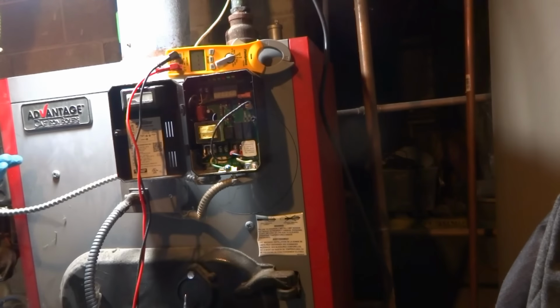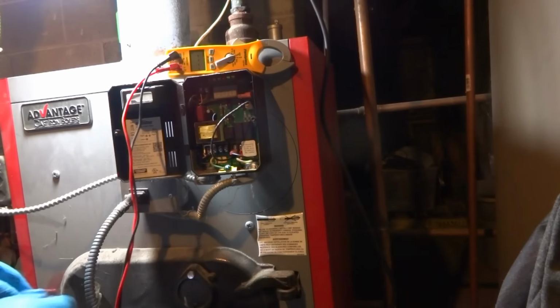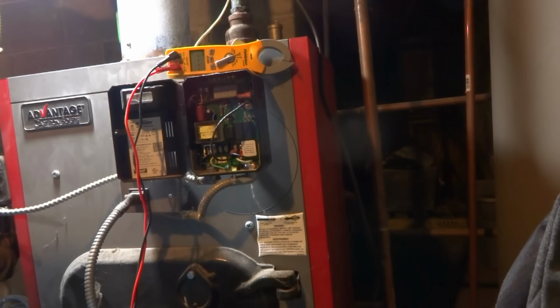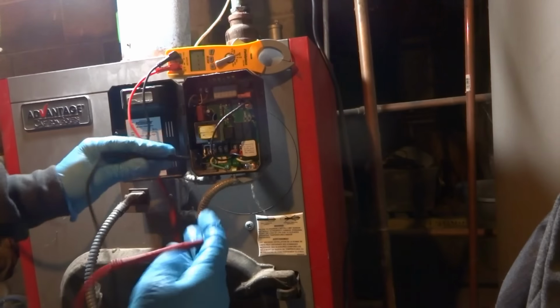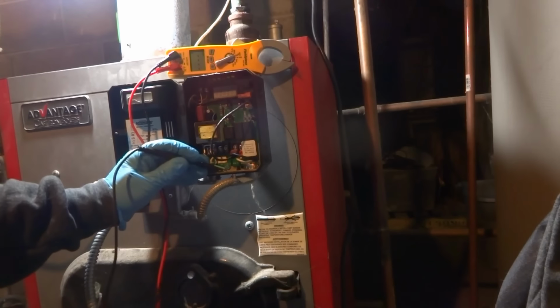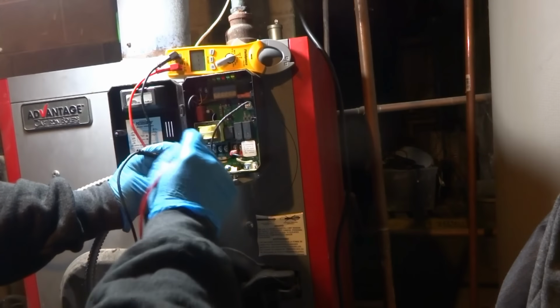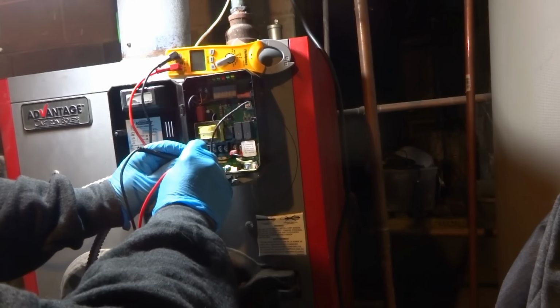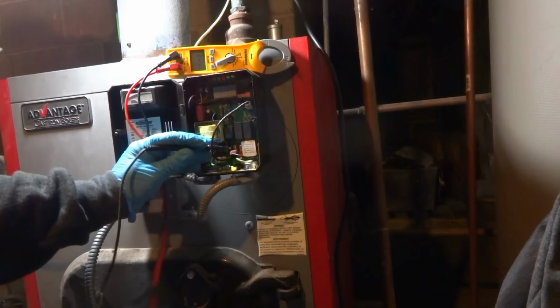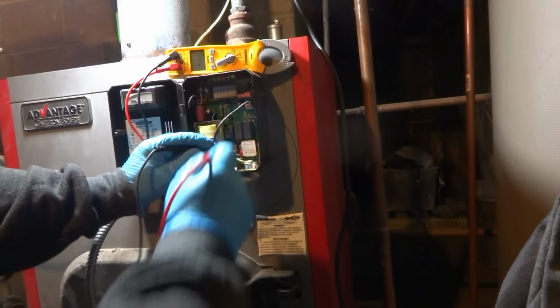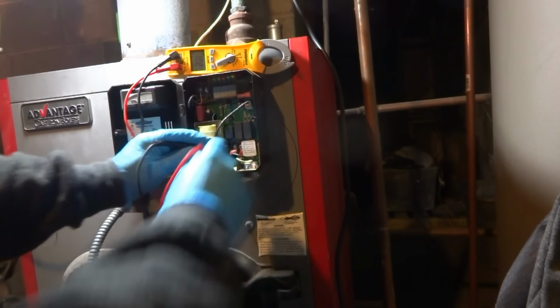You might have a bad switch here or something. Oh, this switch you think is bad? Well, we're going to check that. When I checked, like I said, I changed the breaker because I thought the breaker was bad. No, let's do it again here. Okay, watch, I'm on ground. Yep, right? Yes sir. And that's the line coming in off that switch, off this box here. Okay, hear it? Yeah, now, so if I go to the burner... nothing. So that switch is no good.